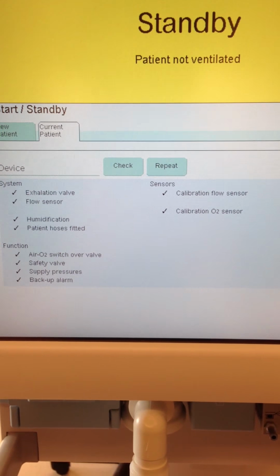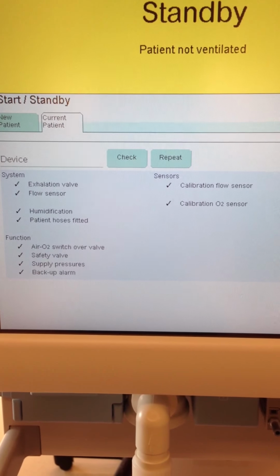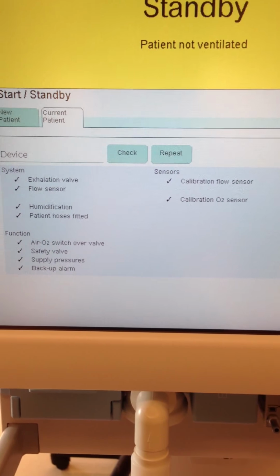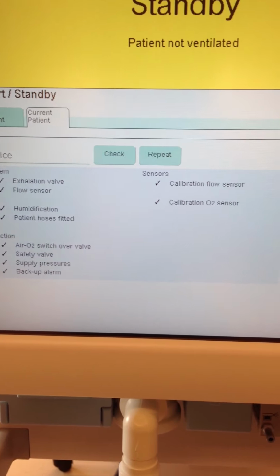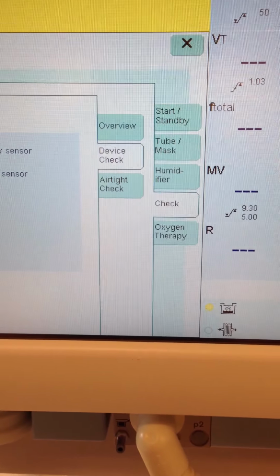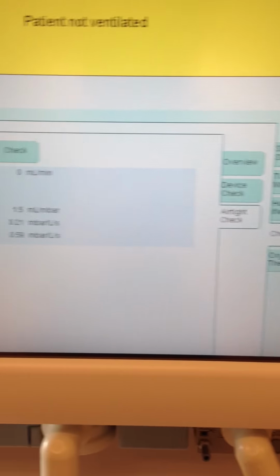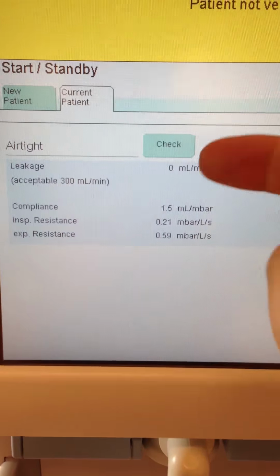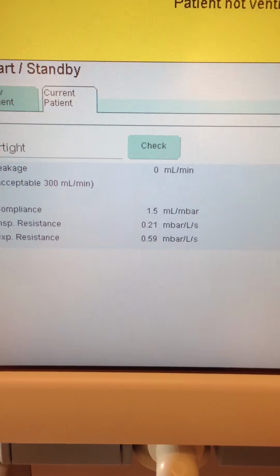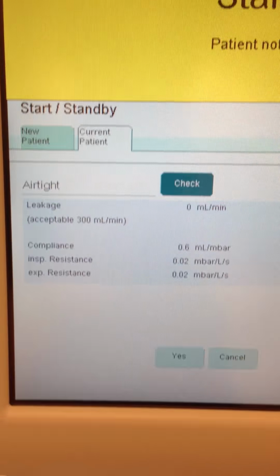Okay, so you can see we've passed. There's check marks on all of our tests that we've run on our device check. What we'll do next is we're going to check the circuit. So we're going to go over here to the airtight check and make sure there's no leak in the circuit. So click that. Same idea. This is going to go through a number of different tests. We're going to start by hitting check. Look up at our prompt.